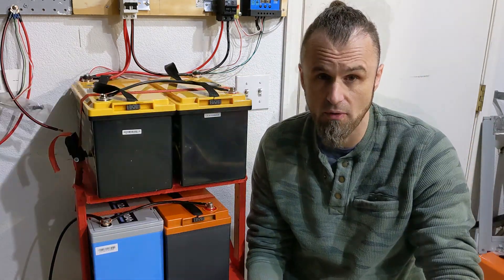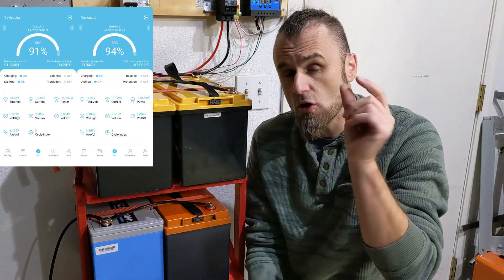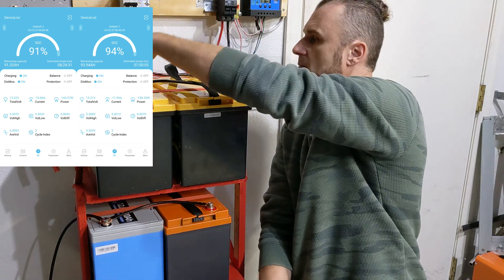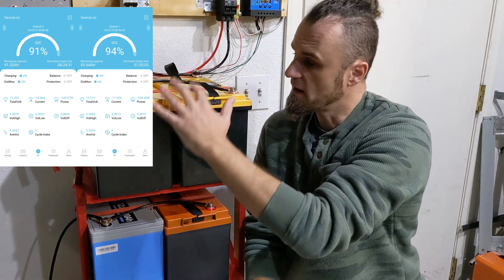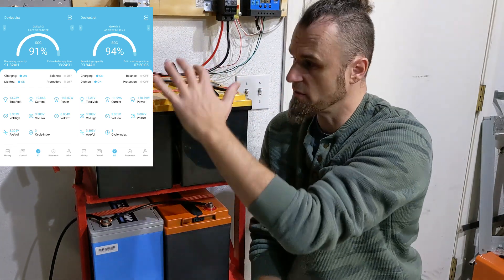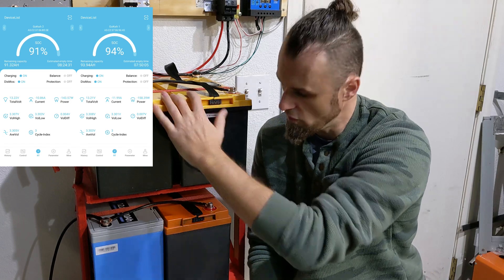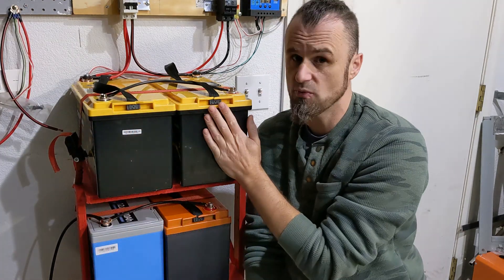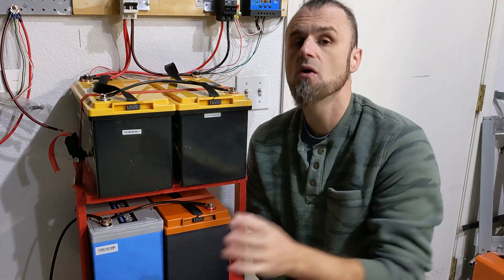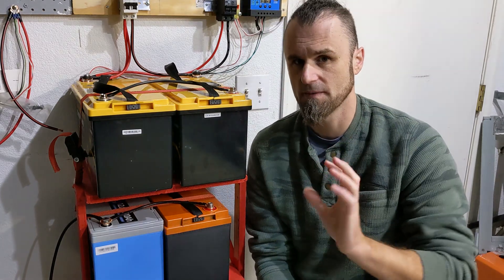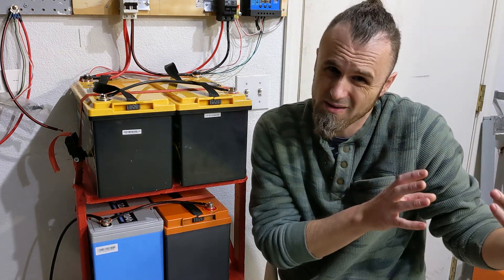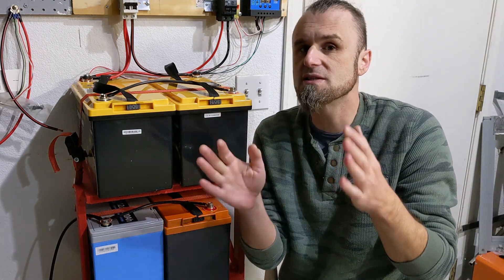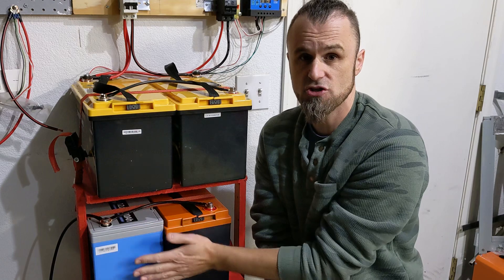So what is happening right now: these two batteries are in sync, slow drift between them but not too big. These batteries are connected with two pigtails coming out over here. They are in sync with this battery. So if this one is 26.6 volts, these will be 26.6 volts. This one does not control this one, this one does not control this one. So these will have their own drift. Some of them will go a little bit more voltage and some will have a little bit less voltage, but they will make that 26.6 because they always balance each other. The two rows balance each other.